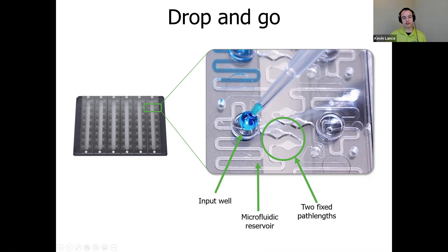After the plate is loaded into the instrument, the circuit is read first when empty. That removes any absorbance contributions from the plastic. Then a pump applies a small vacuum which moves the sample into the microcuvettes to be read, shown by the green circle in the image. Because the circuit has fixed path lengths, it can make very precise and accurate reads.